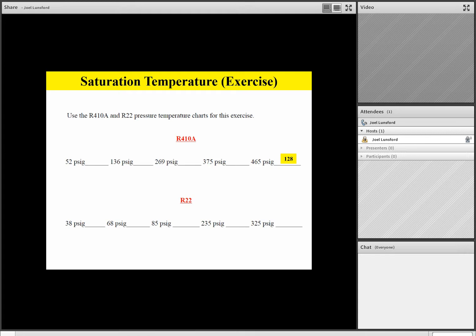you're going to notice there's going to be some R22 columns. So let's do it together. So at 38 PSIG for R22, what is the pressure temperature conversion at 38 PSIG? Good, about 16 degrees. Now remember, team, just round up or round down to the nearest value, to the whole value. It's important that we get close, but if we're within a half a degree or even 1 degree, that's close enough for field work.